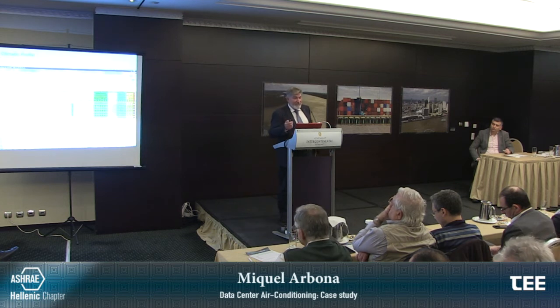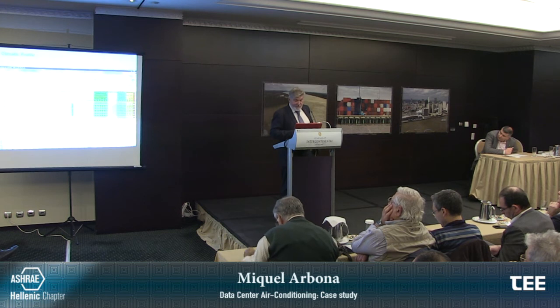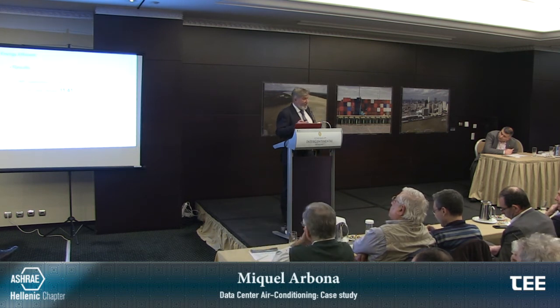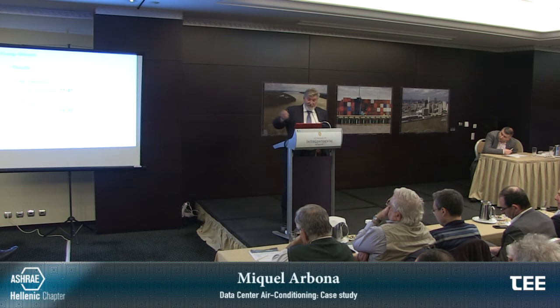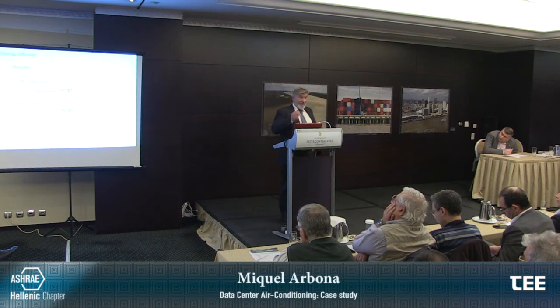Of course, you have to make a lot of numbers. You have to study the climate profile to see the temperature and humidity, and what happens with the system. At the end the result is that for a supply/return of 17/34, 17 is very low, but at that time they were thinking about 17. Now they are thinking more in 23 or 25. But you can see the yearly average EER was 11.4. And with higher temperature, of course, 16, which is not bad, but it's not just the compressor, it's the whole system, because you have the compressor, you have the fans, everything is inside.